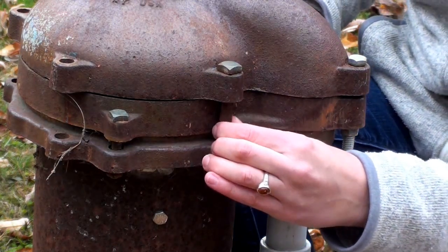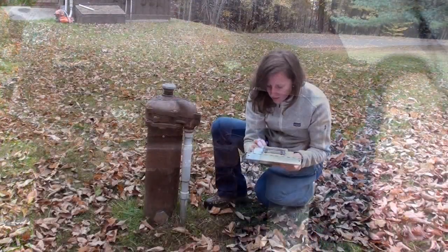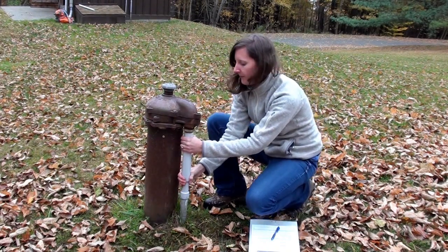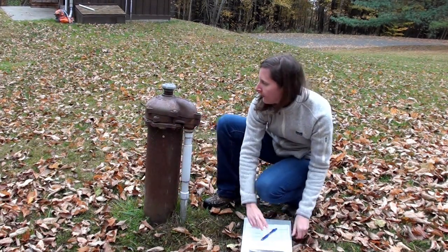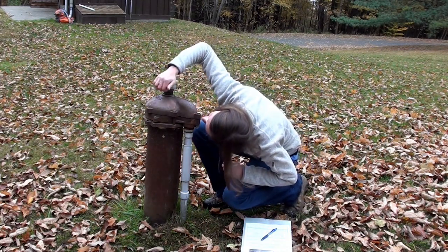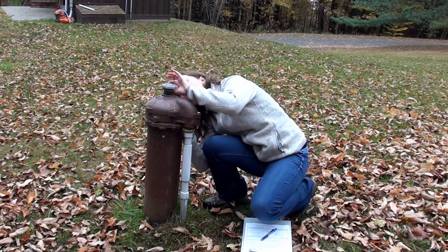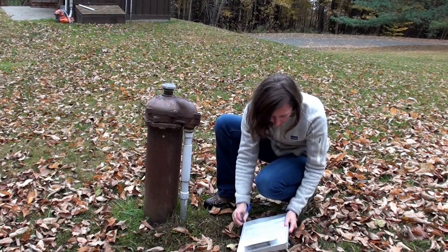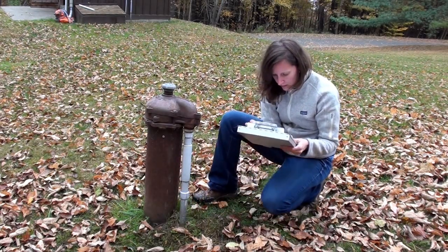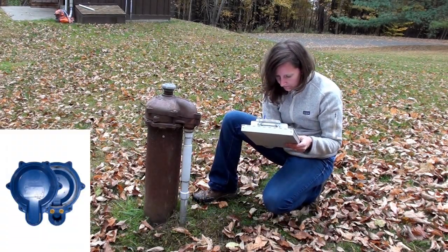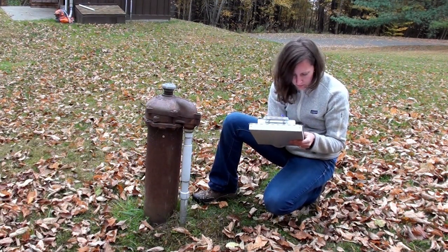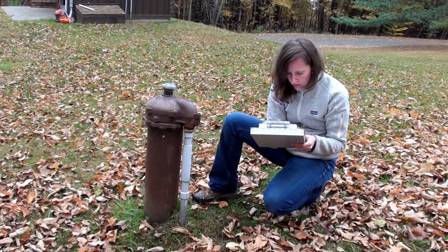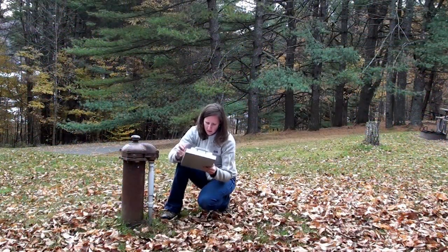Look at the electrical conduit to make sure that it is not cracked and that the connection with the well cap is tight. Also, look to make sure the cap has a vent screen that is intact. In this example, the cap has a mushroom-style vent, which has an internal screen. Other caps have the vent underneath, near where the electrical conduit attaches. Even the smallest of voids or cracks in the conduits, caps, or vents could allow contamination into the system.